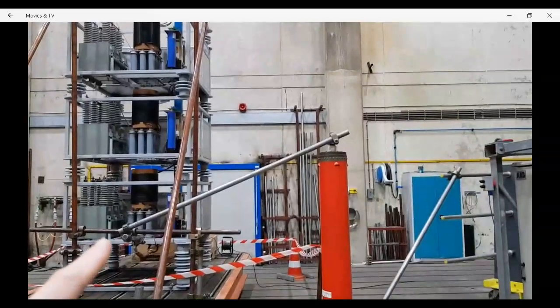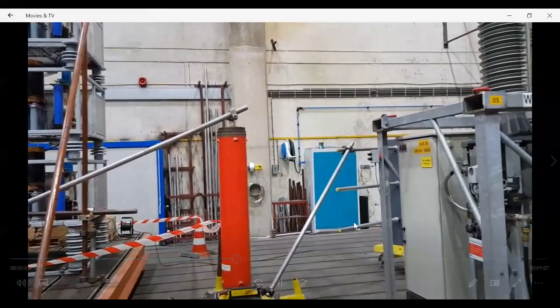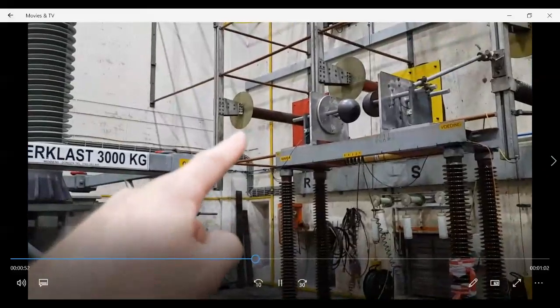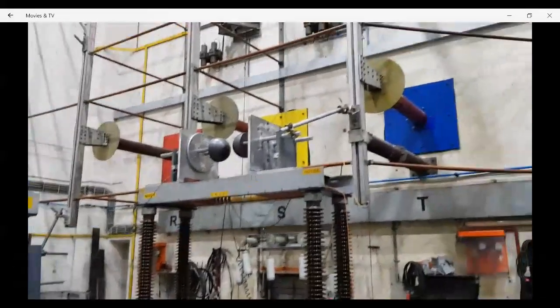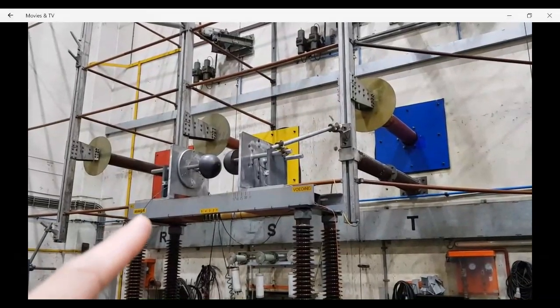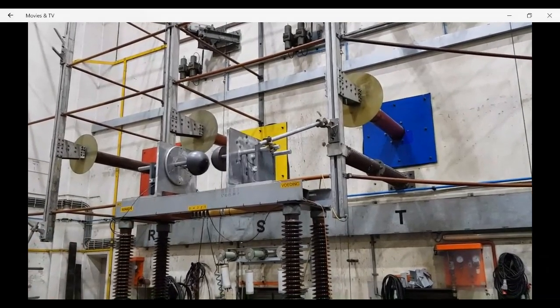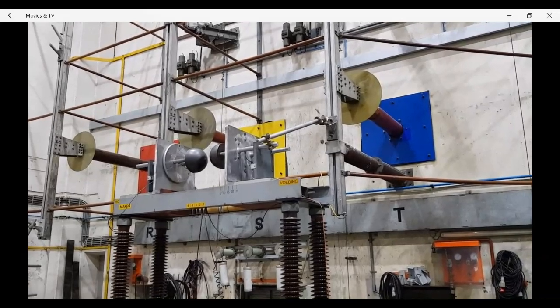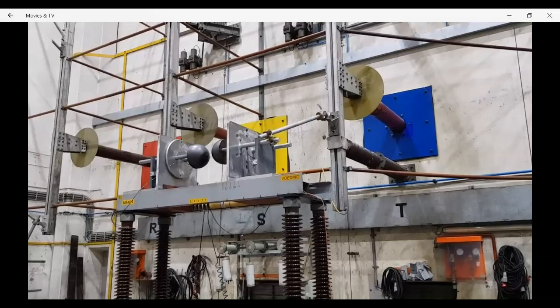The return path is from the bottom of the test object through this coaxial shunt, then going back to the other side of the rail and passing through the red wall bushing. Also connected across the supply is this bypass protection circuit, consisting of a triggered spark gap, which will bypass the short circuit current in case of an overcurrent or another calamity, therefore protecting the test object.